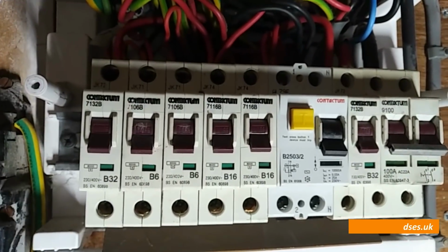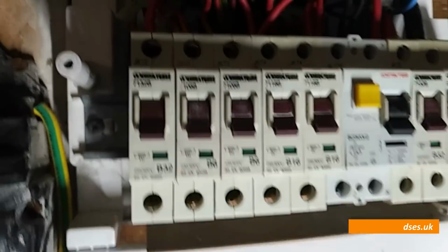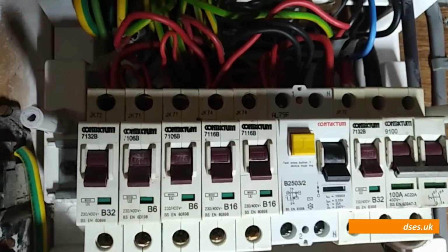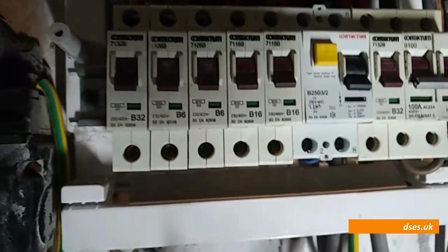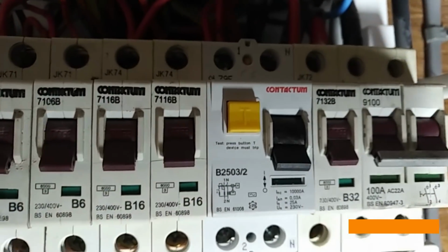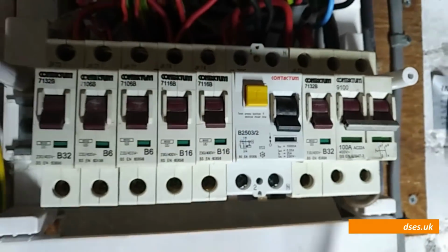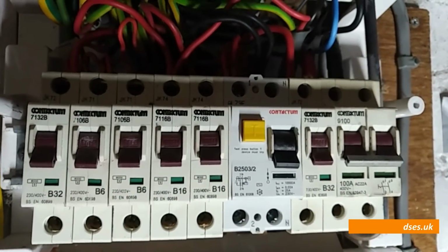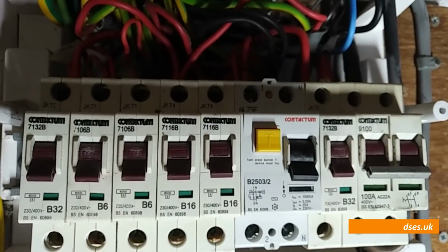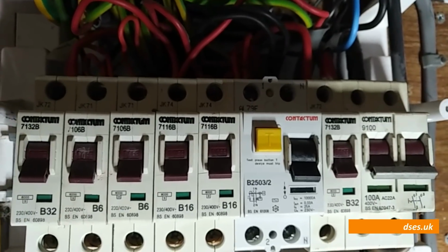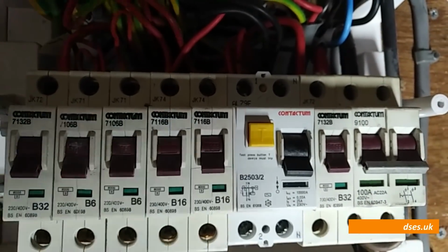So this is a bit of a problem, obviously, and it's a bit confusing because Contactum have used this model code for this device: B2503/2. So on the face of it, you do think, okay, it's a double width RCBO rated at 25 amps, B curve, 30 milliamp, but it's not.